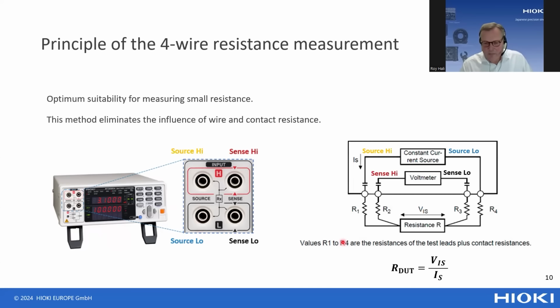The 4-wire method works like this. You have 4 contacts: source high, source low, sense high, and sense low. The source circuit is used to carry the test current to the battery, so the test current flows through this circuit through the battery.